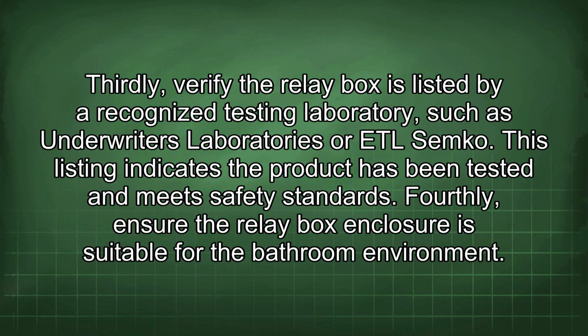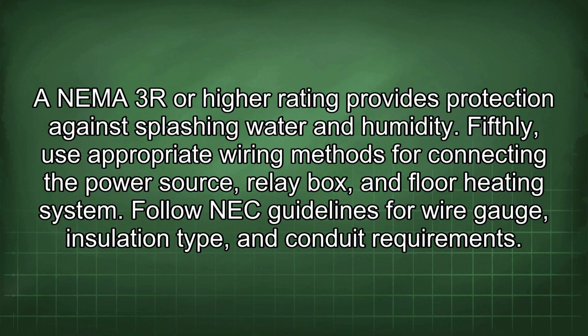Thirdly, verify the relay box is listed by a recognized testing laboratory, such as Underwriters Laboratories or ETL Semko. This listing indicates the product has been tested and meets safety standards. Fourthly, ensure the relay box enclosure is suitable for the bathroom environment. A NEMA 3R or higher rating provides protection against splashing water and humidity. Fifthly, use appropriate wiring methods for connecting the power source, relay box, and floor heating system. Follow NEC guidelines for wire gauge, insulation type, and conduit requirements.